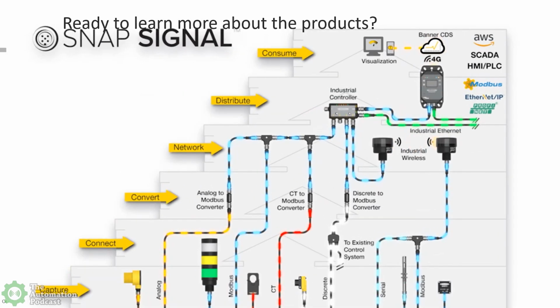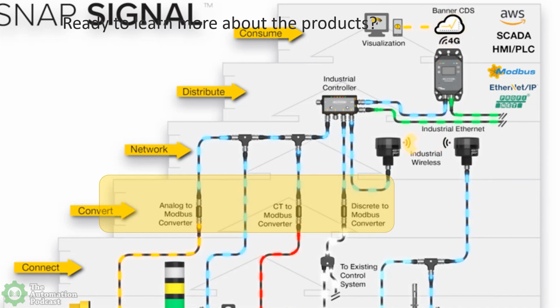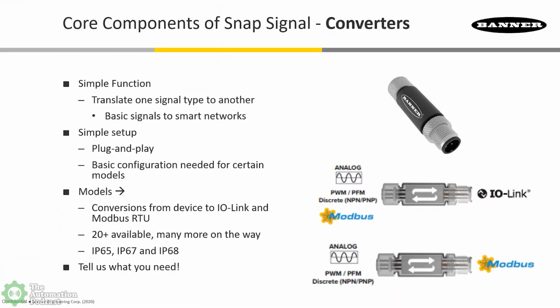Diving into our converters: they function simply, converting basic signals from one signal type to another. We're able to take in signals like discrete sensor signals, analog sensor signals—whether 4 to 20 or 0 to 10 volt, whether discrete NPN or PNP proximity sensors, or a temperature sensor input—and convert those to smart networks like IO-Link and Modbus RTU.